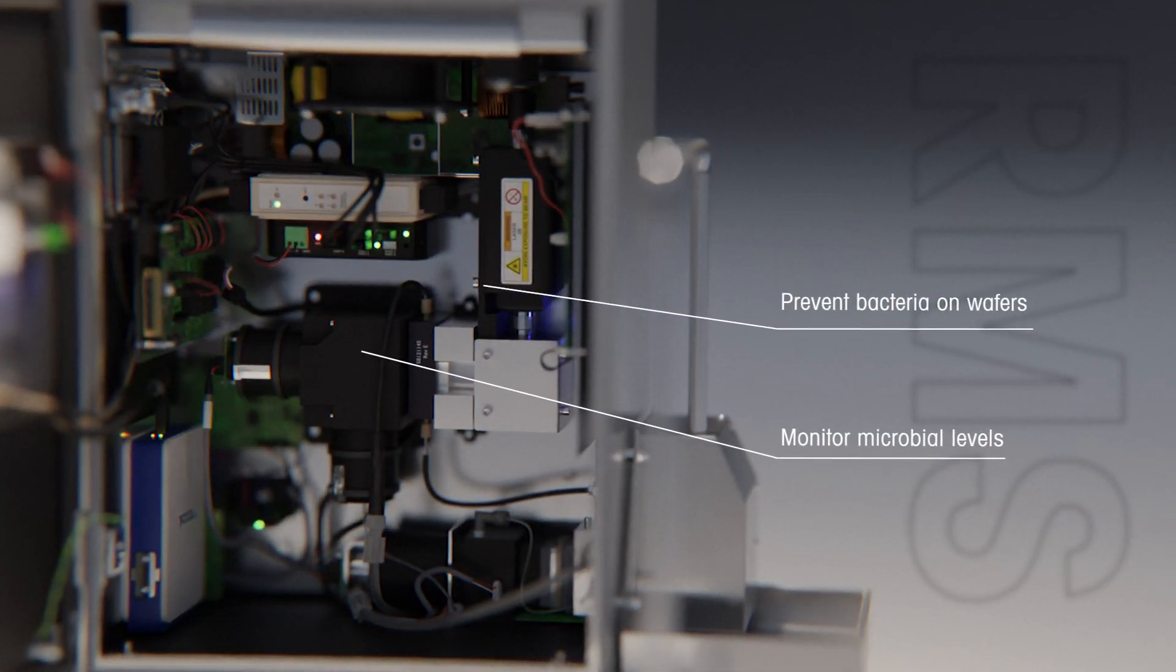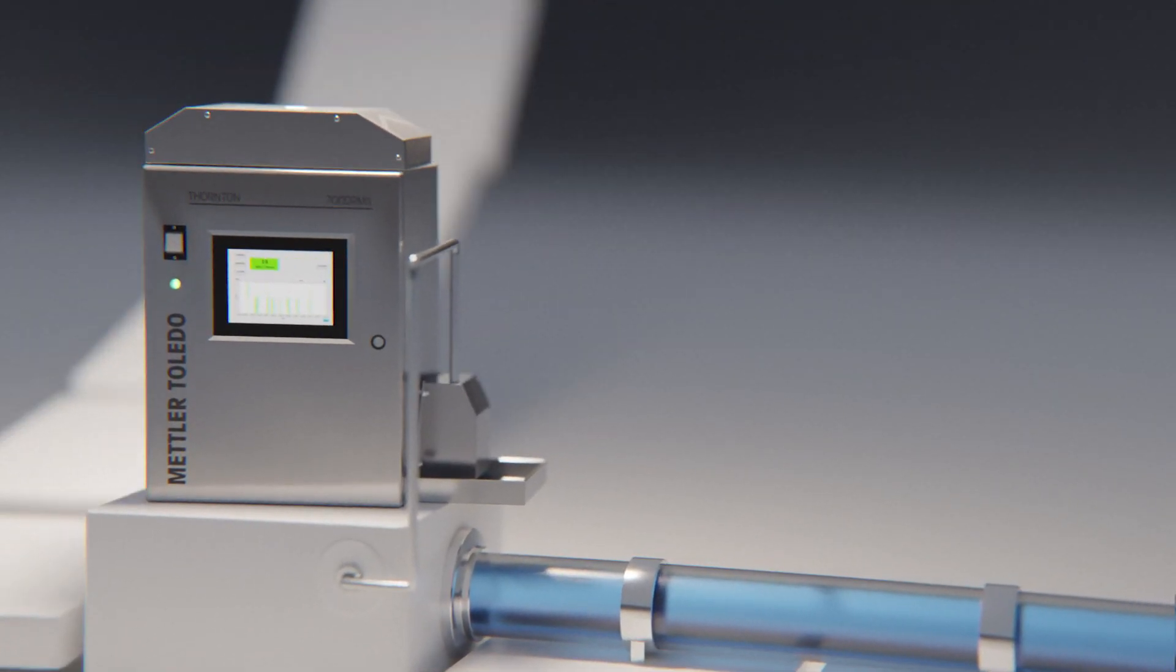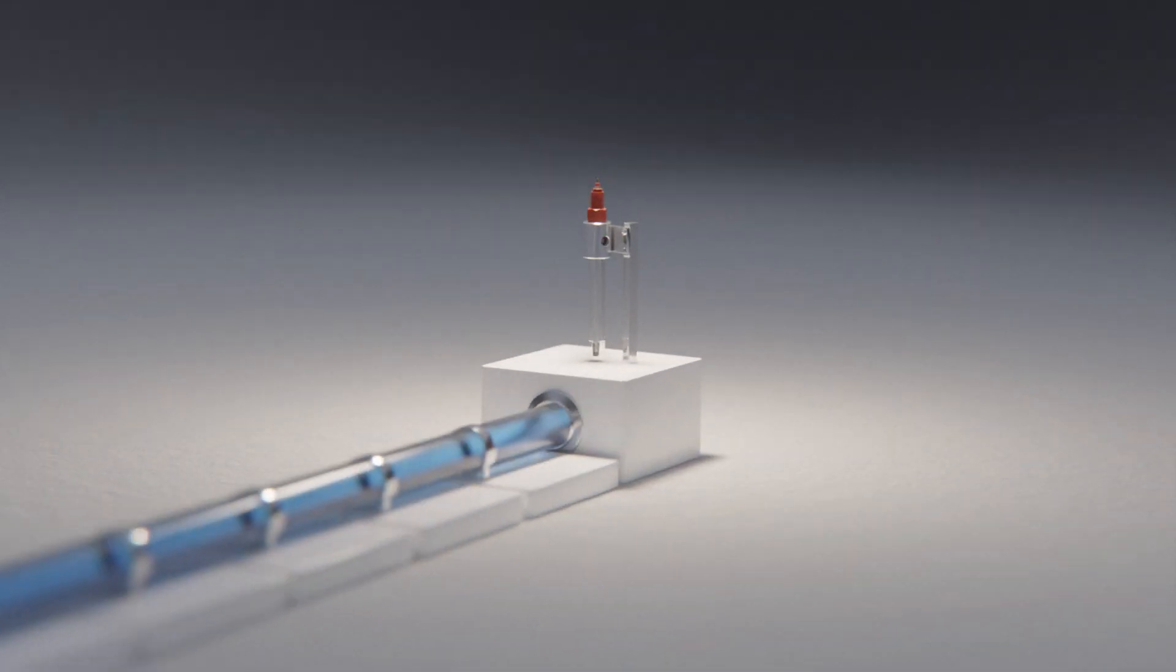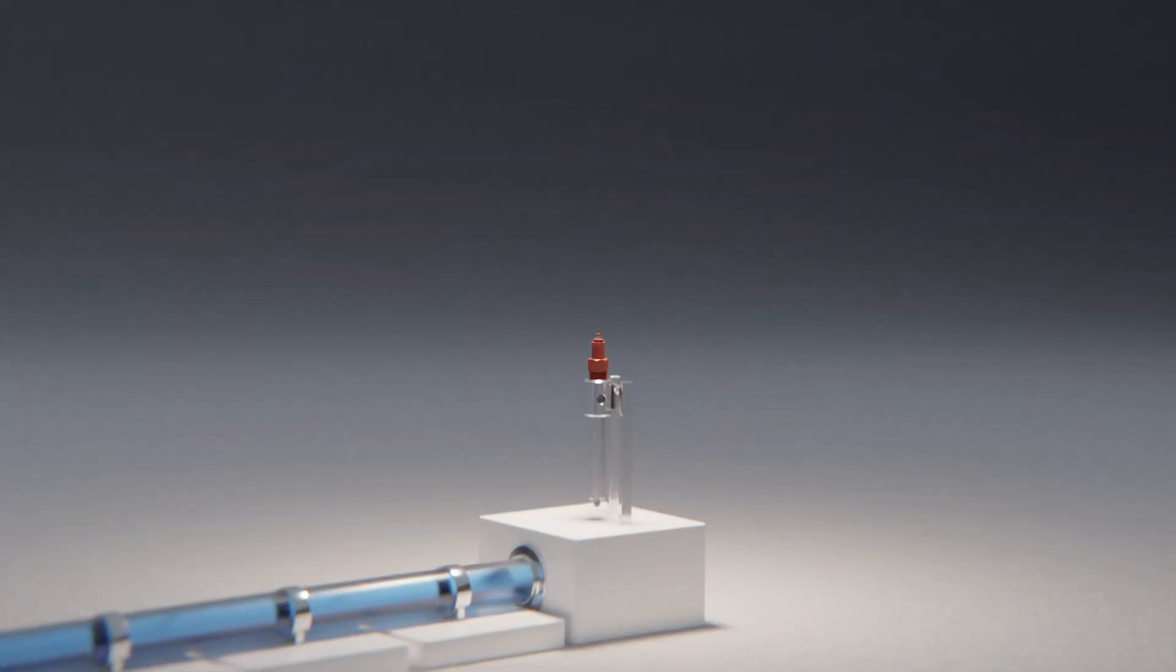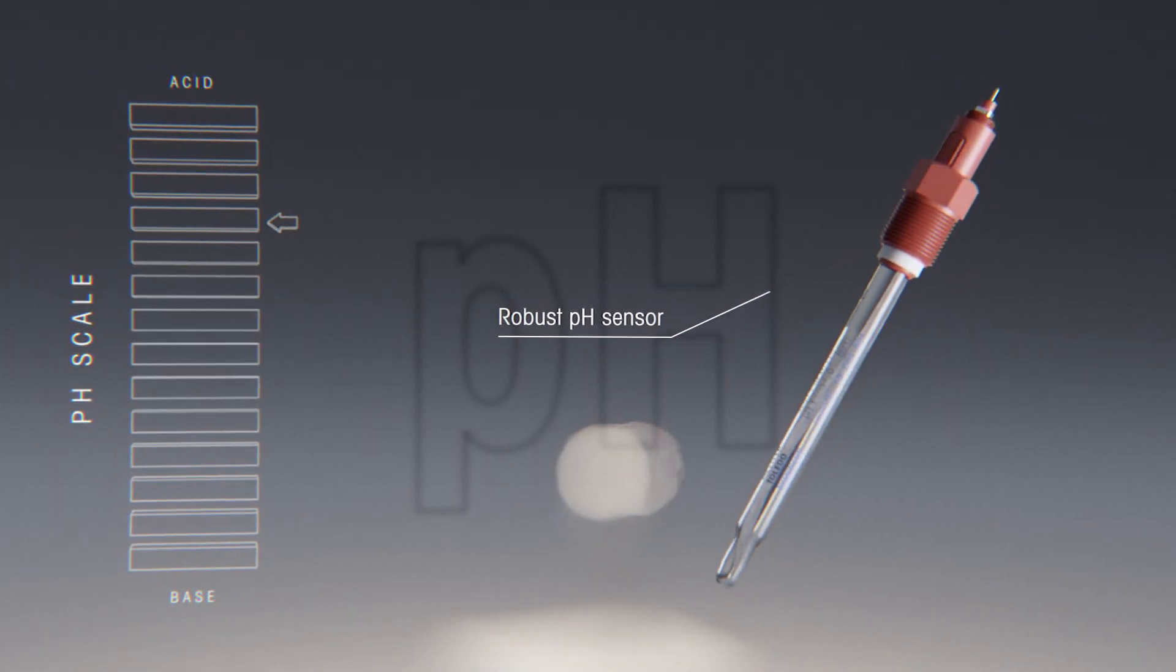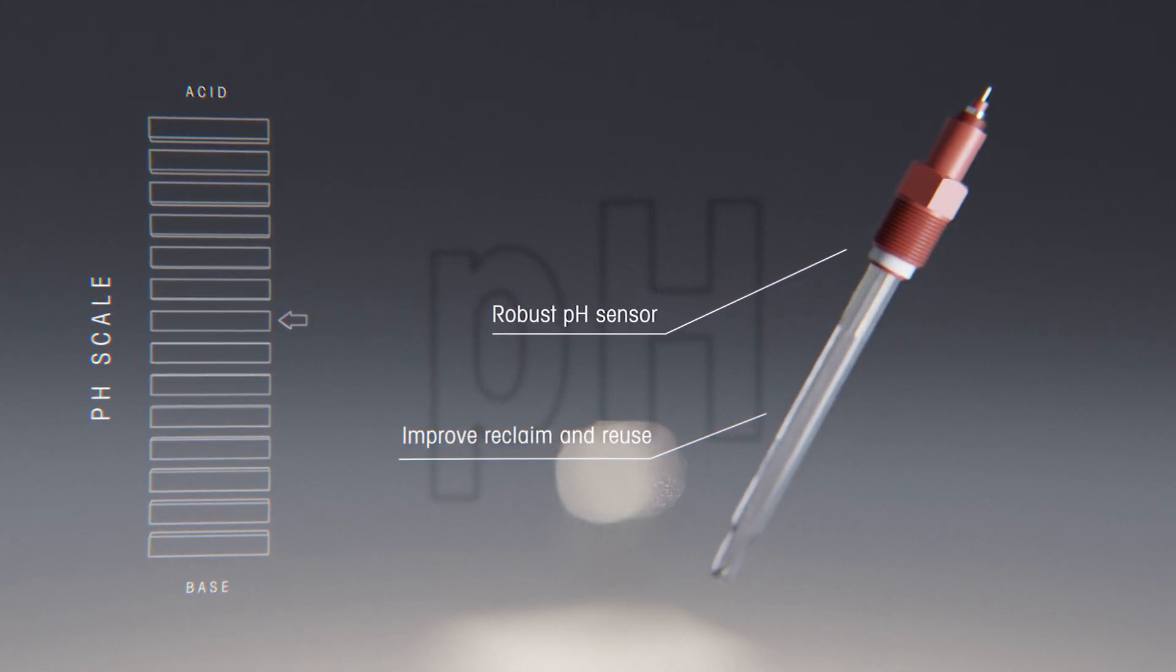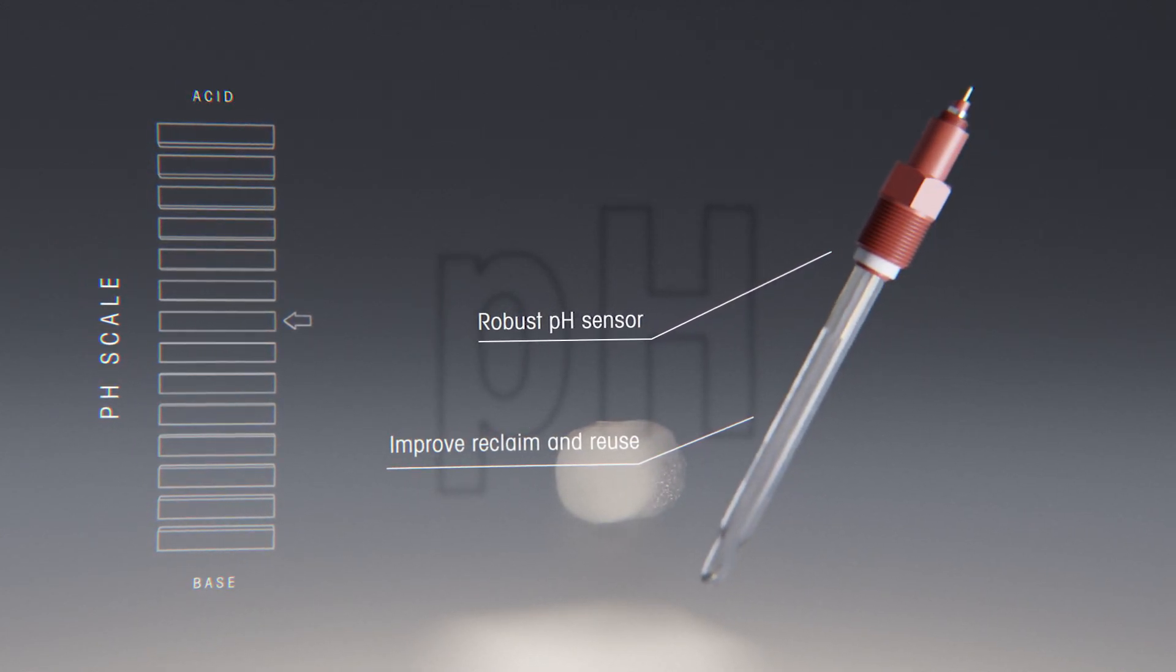When it comes to reclaiming and reusing water, waste streams from production areas contain a variety of chemicals that must be neutralized or removed before the water can be treated further. Hydrofluoric acid is used in several wafer processing steps, and the neutralization of HF wastewater requires a pH sensor robust enough to handle the acidic and corrosive conditions.